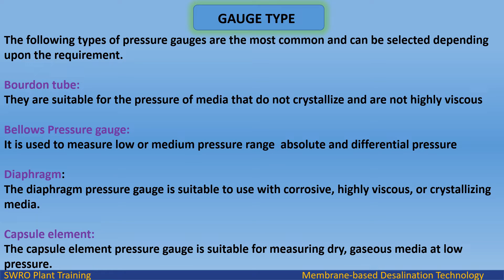Gauge type: The following types of pressure gauges are the most common. Bourdon tube: suitable for media that do not crystallize and are not highly viscous. Bellows pressure gauge: used to measure low or medium pressure range, absolute and differential pressure. Diaphragm: suitable for use with corrosive, highly viscous, or crystallizing media. Capsule element: suitable for measuring dry, gaseous media at low pressure.